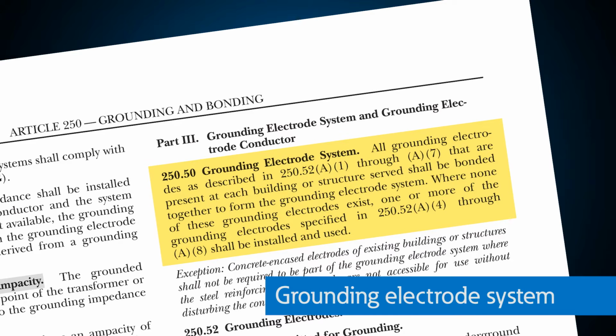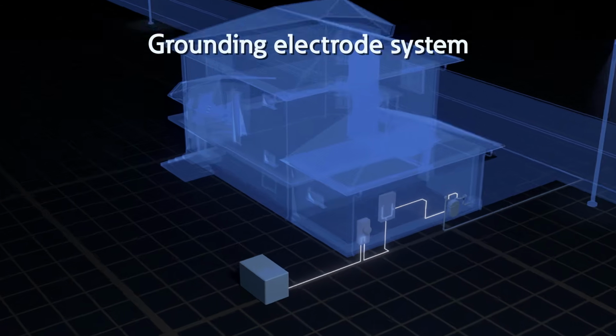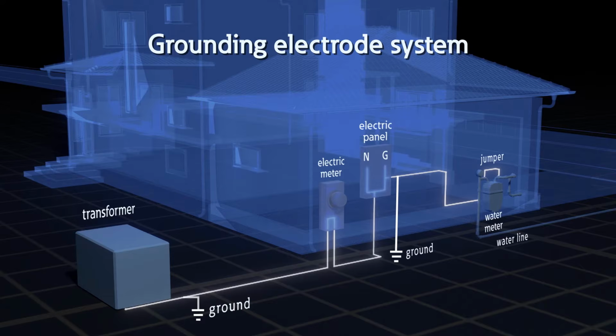And what the National Electrical Code tells us is that we need to connect all of those grounding electrodes together, and we create what the NEC calls the grounding electrode system. The grounding electrode system is when we pull all of those grounding electrodes together. So every grounding electrode that we have on that site, whether it be the Ufer ground, the water pipe, or other means that are identified in the National Electrical Code, we have to pull all of those together as a system. And that we call the grounding electrode system.